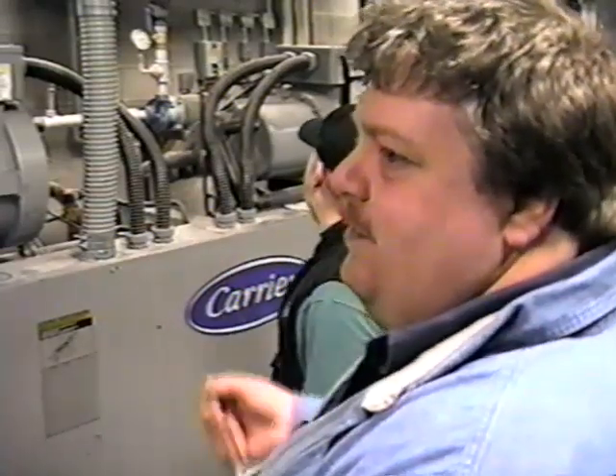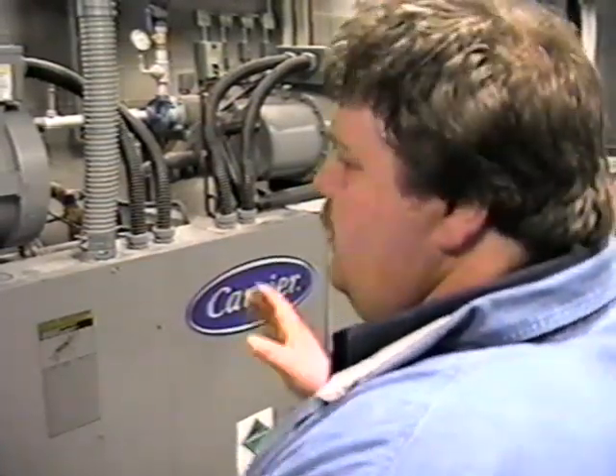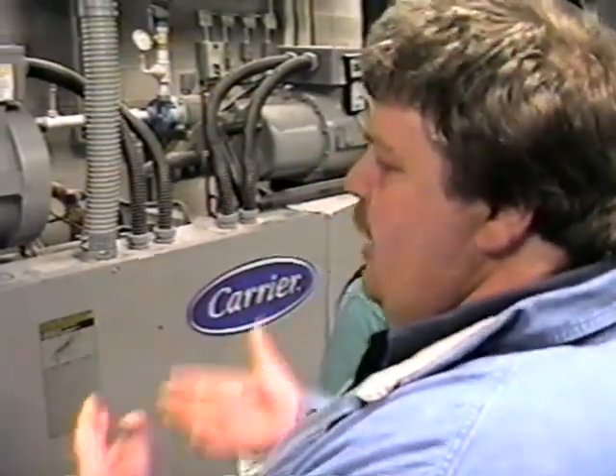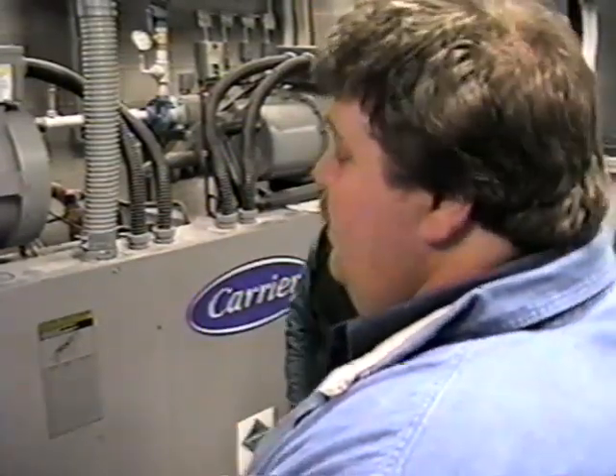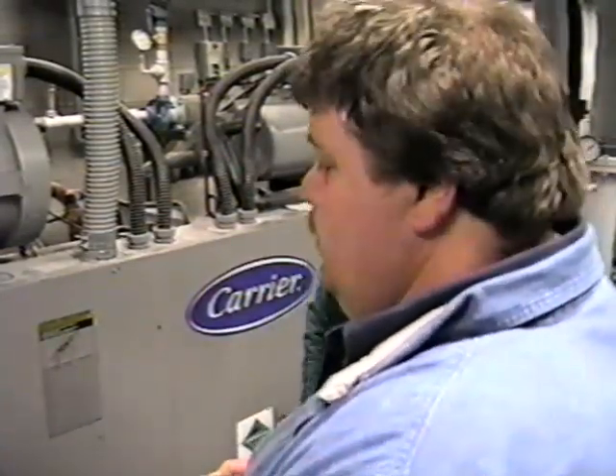That's the reason for that, because you've still got high discharge pressure and a low suction there, and because of that pressure difference, you're still moving refrigerant through a metering device, and you could freeze something up.